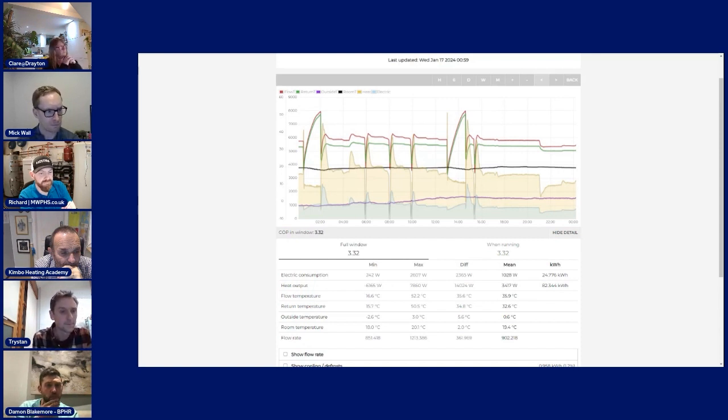We've got a Mixergy in, so we've been playing around with this plate for 18 months. We were frustrated with the Mixergy, we couldn't get it working. After everything we've tried to swap and change, we found that the Mixergy also takes into account that you've got a full house, and when they recharge the cylinder, to get the best COP from hot water we need to drain it fuller, then load it on eco mode, so the heat pump's pulling back a little bit, which gives more transfer across that plate. Without all this data we would never have nailed this. We would have just been unhappy with the Mixergy. Now that Mixergy is running as well as coiled cylinders in that specific time.